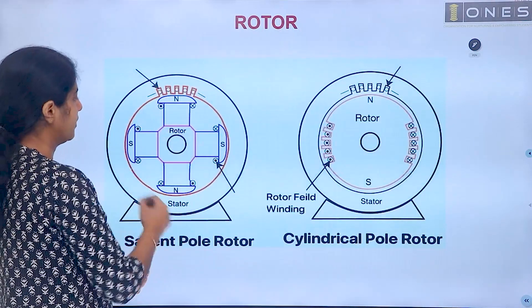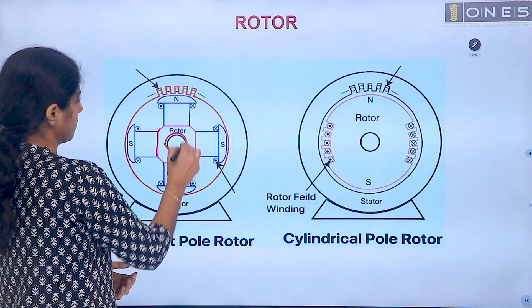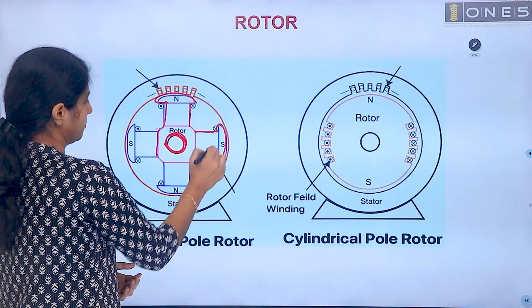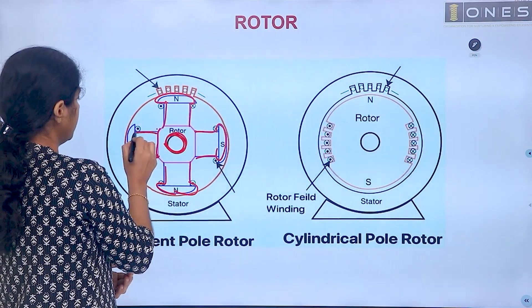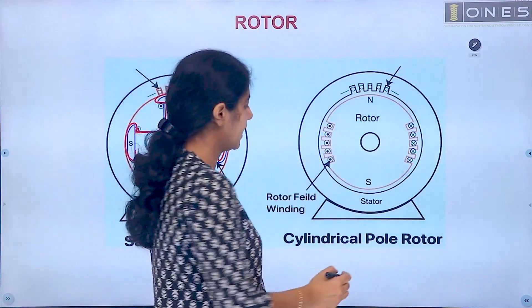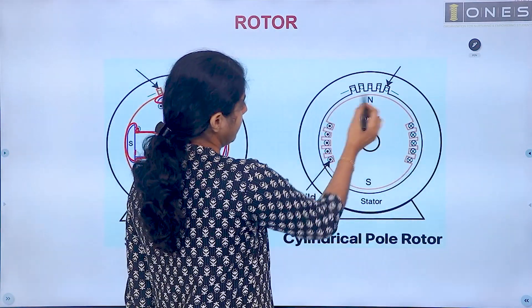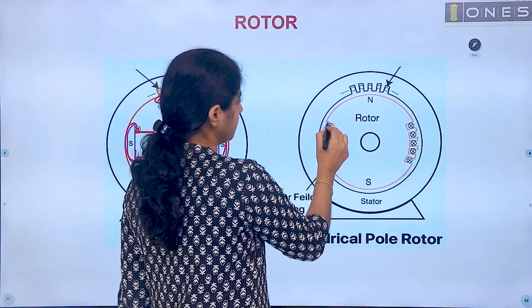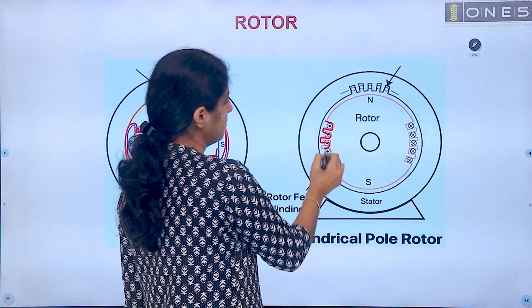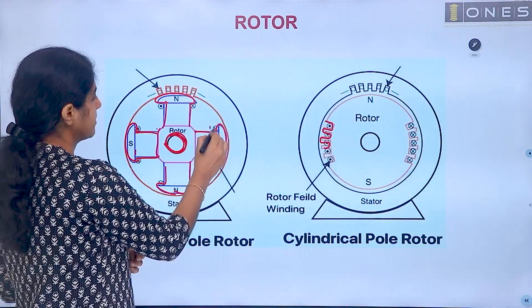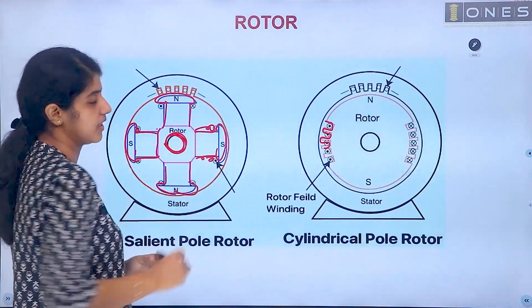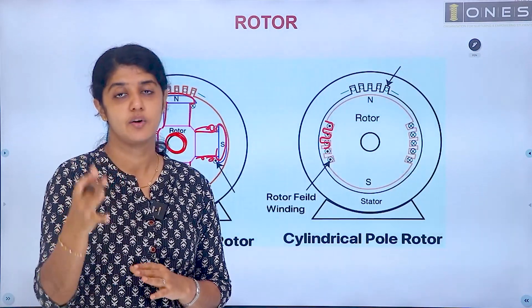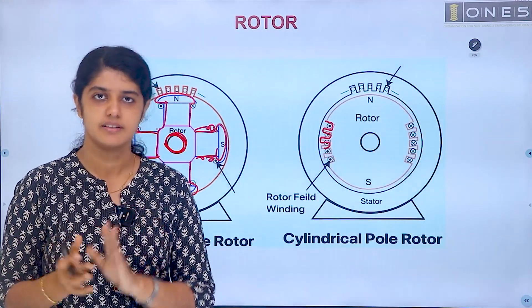This is the rotor shaft, and this is the projecting pole — that is the salient pole structure. This is the non-salient pole structure, which uses a cylindrical rotor. In this cylindrical rotor, the field windings are placed in slots. We have DC excitation for the field windings, creating north pole and south pole polarity.